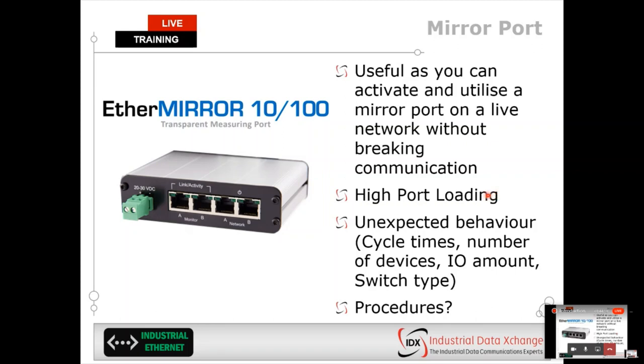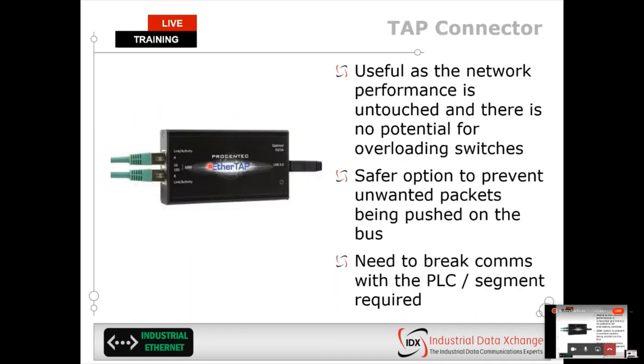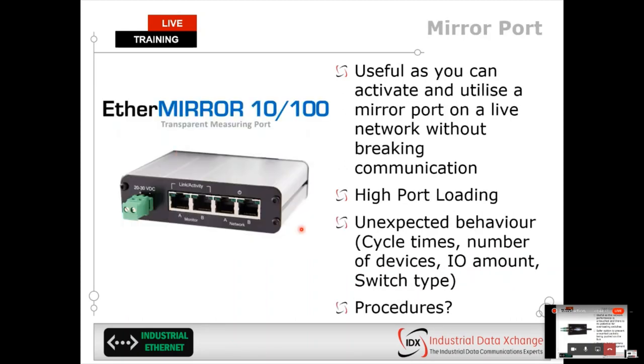So now, if you wanted a permanent tap connection point, since we said the risk is that we need to unplug the PLC to plug a tap connector in, I can install a low-cost component called an EtherMirror. What an EtherMirror does is the PLC plugs into link A, and the rest of the network plugs into link B. It's part of the network, stays permanently connected, a low-cost network component.